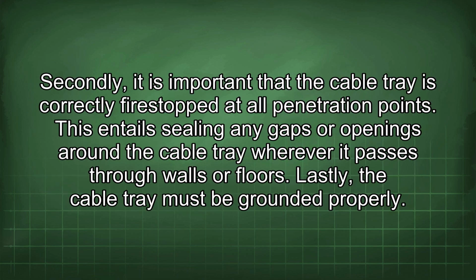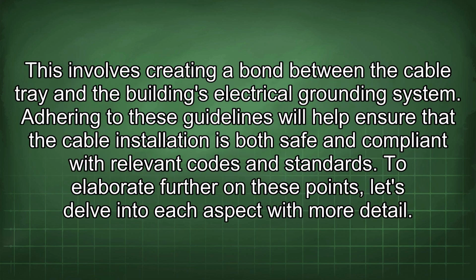Secondly, it is important that the cable tray is correctly fire-stopped at all penetration points. This entails sealing any gaps or openings around the cable tray wherever it passes through walls or floors. Lastly, the cable tray must be grounded properly. This involves creating a bond between the cable tray and the building's electrical grounding system. Adhering to these guidelines will help ensure that the cable installation is both safe and compliant with relevant codes and standards. To elaborate further on these points, let's delve into each aspect with more detail.